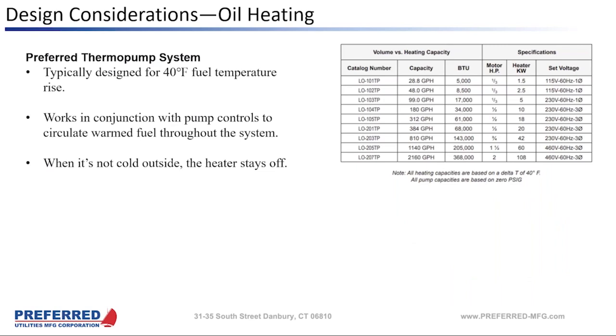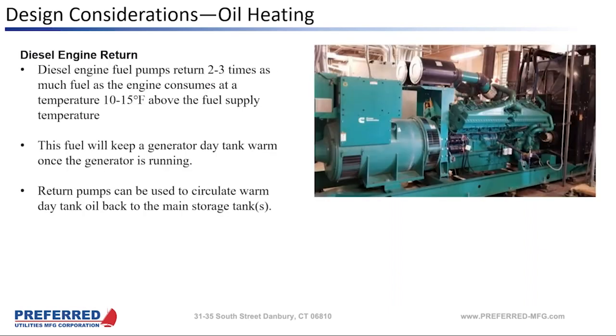So this is the sizing of the Thermopumps. They come in sizes from a 101 to a 207, and the 101 and 207 refer to the size of the pumps. And then the heaters are sized for a 40-degree difference in fuel temperature, which is what we try to get. And the cool thing about it is, most of the year when it's warm, the heater stays off and it's like it's not even there.